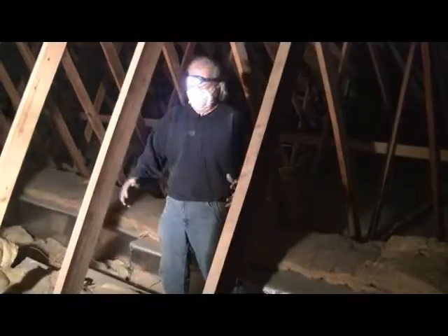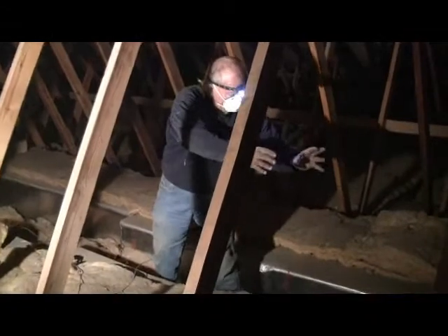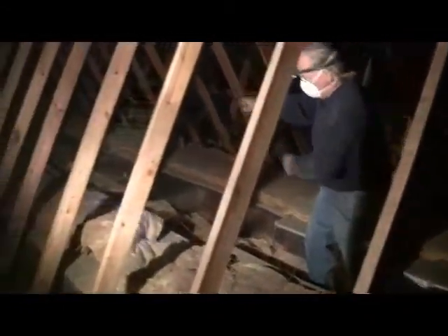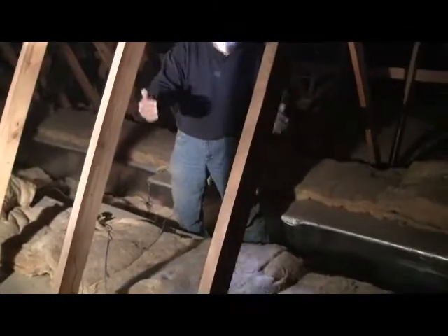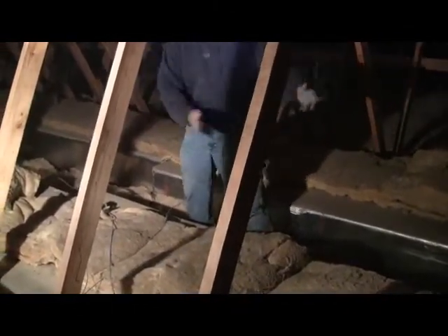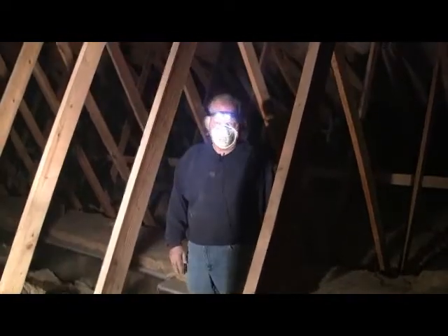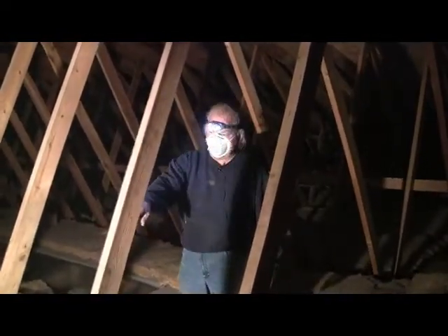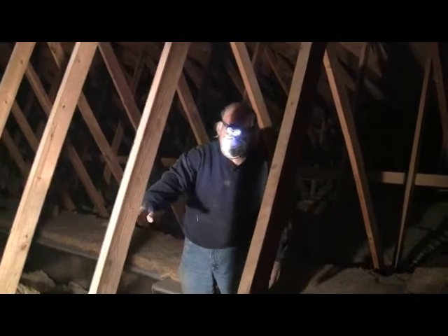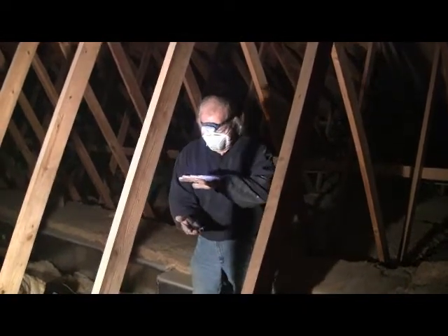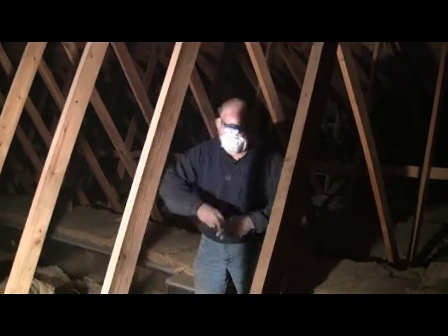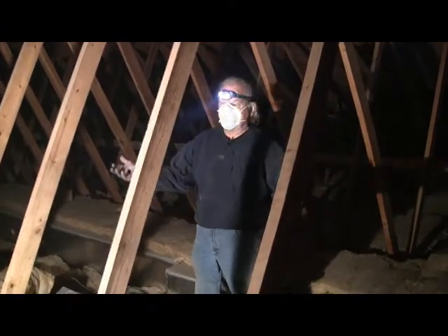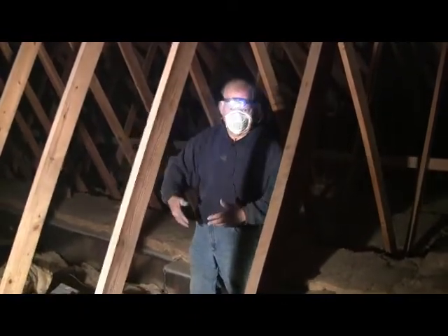So we've got an opportunity. The job that needs to be done to make this work is to work from the very start of the ducting system all the way to the end using a mastic product and a reinforcing tape to seal the ducting system so that it in fact is airtight throughout its entire length. And we need to seal the metal panned areas that Bill is standing on, where the joints are nailed, where the metal is nailed to the rafters. That needs to be sealed as well to stop its capacity to pull air from the attic into the building.